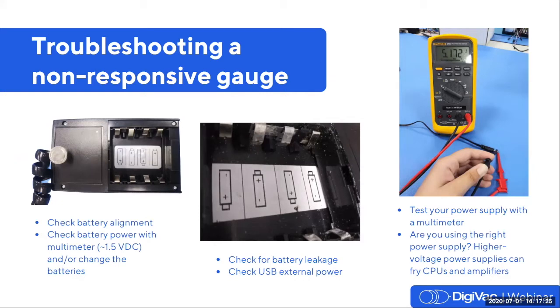If they are, have you used a voltmeter or a battery tester? Even if you haven't been using the gauge, the circuit exerts a small trickle current drain on the batteries, so they may be dead inside the unit, especially if the gauge hasn't been used for a while. Even batteries that are new in the box can be dead already, depending on their age. You can use a standard voltmeter to measure the DC voltage of the battery. AA batteries are 1.5 volts, so the closer to that, the better.